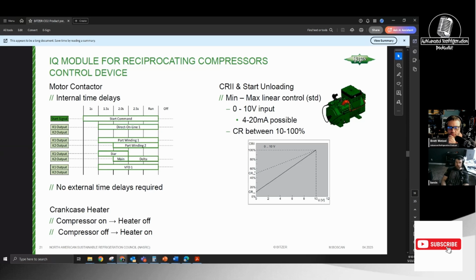Gotcha. And then same thing, you can make it 0 to 10 volts, or you can make it 4 to 20 milliamps. I've been seeing a lot of stuff lately coming out 4 to 20 milliamps, which, I mean, a lot of the control world thinks 0 to 10 is like the peasant control. They do, but you've got to remember a lot of the building controllers run across buildings. Yeah, they do it because it's more accurate. Even though you hear 4 to 20 milliamps, they are using that first 4 milliamps to essentially power up the device, and that's really why. And then you get a more accurate signal, and you only need a 2-wire control versus 3-wire. That extra wire costs so much.